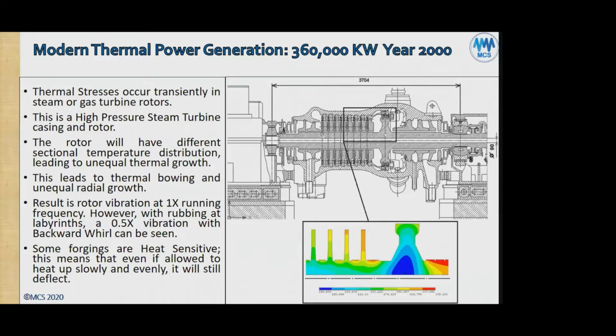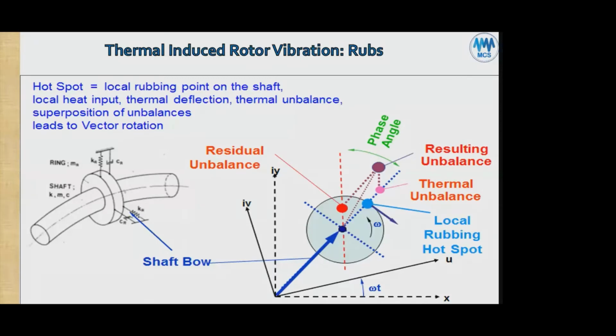So we'll go to the next slide, I hope. Okay. So we go back to the different sources that we discussed. Now we look at one source, rubs. Rubbing causes a hot spot due to friction. So here's our rotor, and originally it came with a residual unbalance, which was not severe. It might have been, for example, causing only 1 mil vibration at 3,000 RPM. Let's assume it's a 50 hertz generator or 50 hertz steam turbine rotor, and it's operating with 1 mil, 25.4 micron vibration.